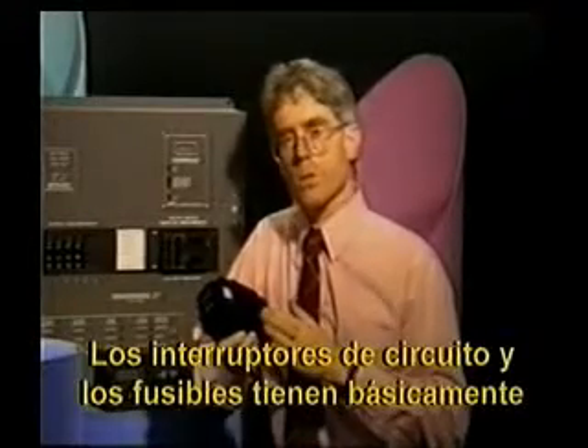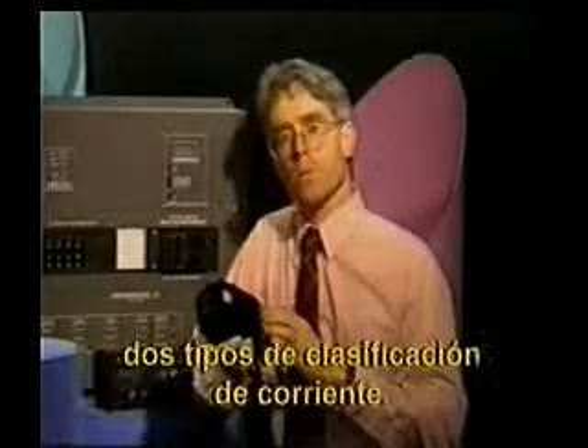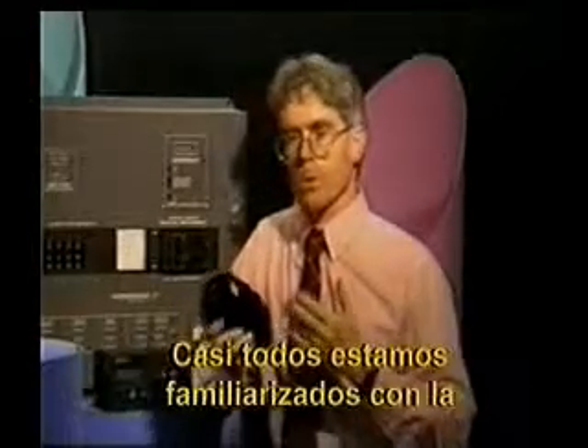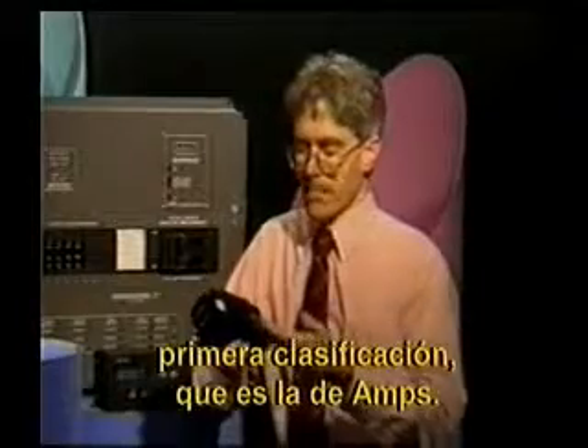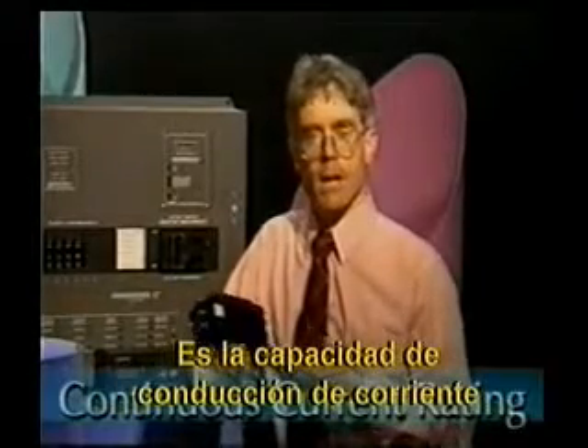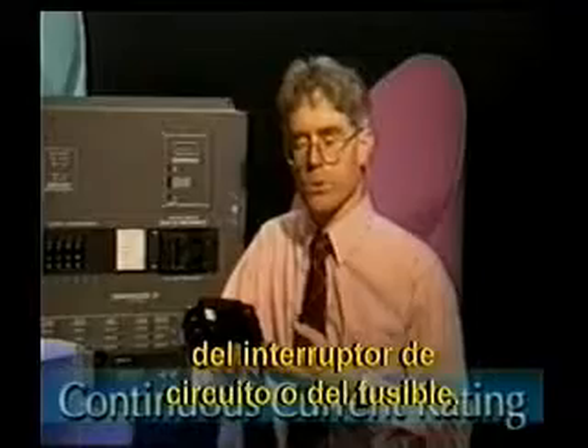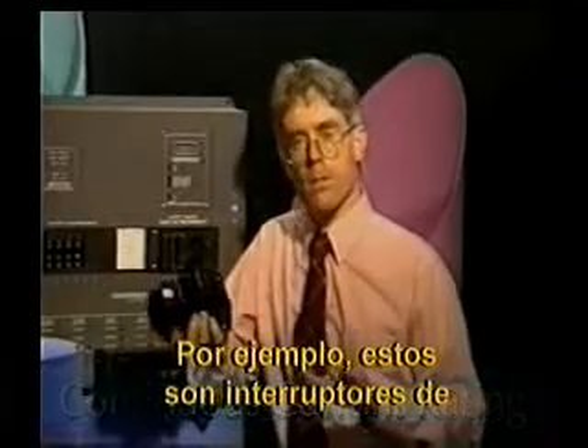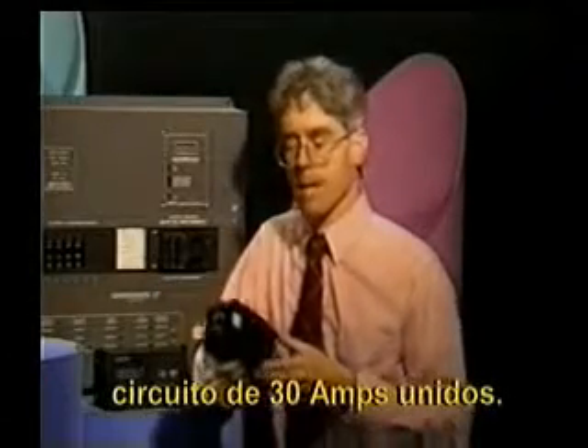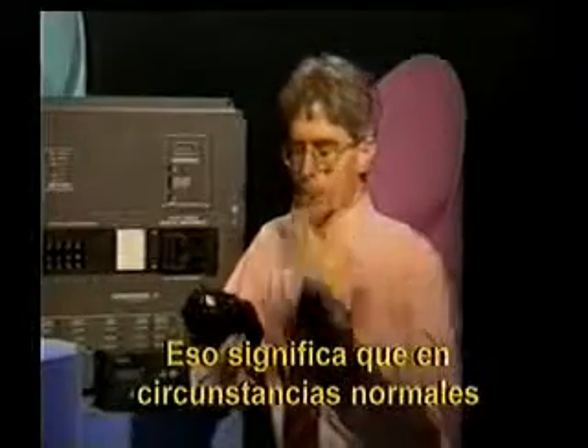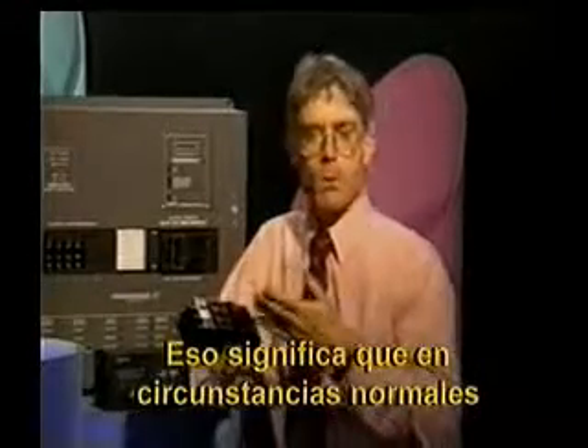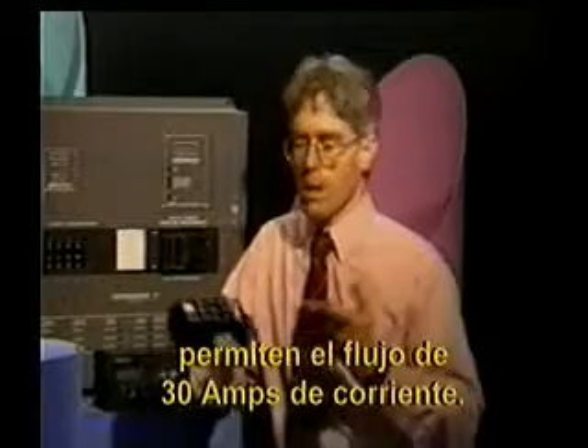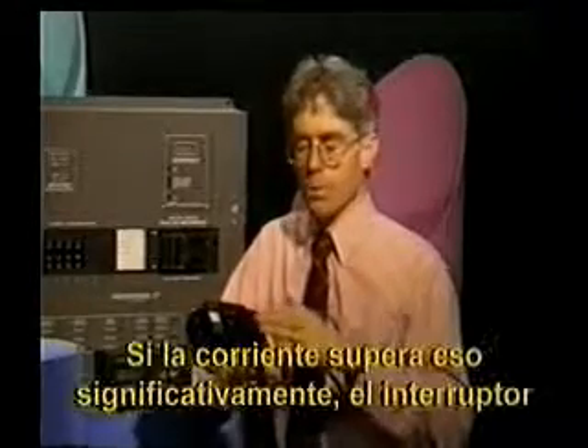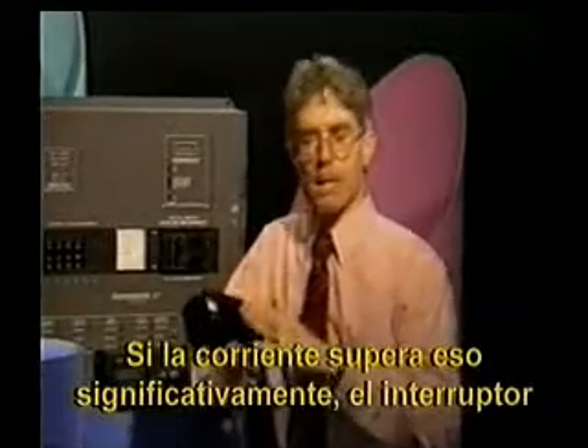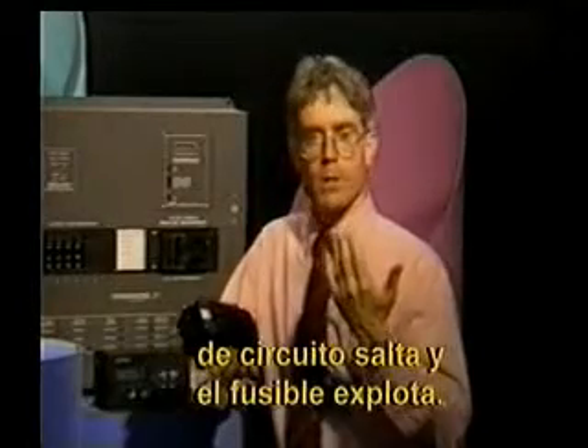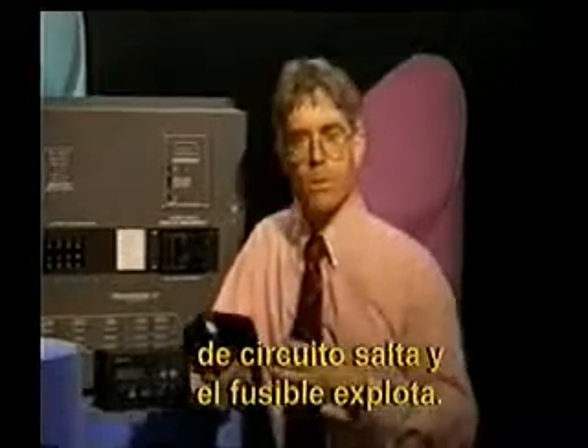Circuit breakers and fuses have basically two kinds of current rating. Most of us are familiar with the first rating, which is the amp rating, the current carrying capability of the circuit breaker or the fuse. For example, these are 30 amp circuit breakers ganged together. That intuitively means that they should allow 30 and maybe a little bit more amps of current to flow under normal circumstances. If the current rises above that rating significantly, the circuit breaker should trip, the fuse should blow.